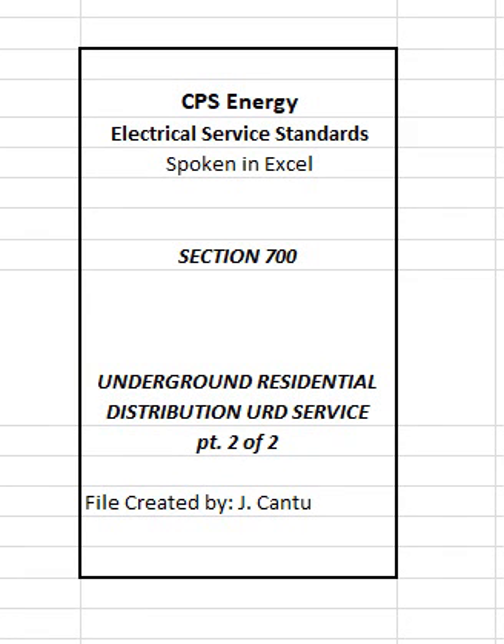704 Conduit depth. Conduit trench shall be of adequate depth and width to accommodate minimum conduit dimensions with 24 inches of coverage on top of service lateral conduits. Exception: where CPS Energy deems it necessary to route service lateral conduits and conductors in public right-of-way, the depth shall be a minimum of 36 inches to the top of conduits from final grade.